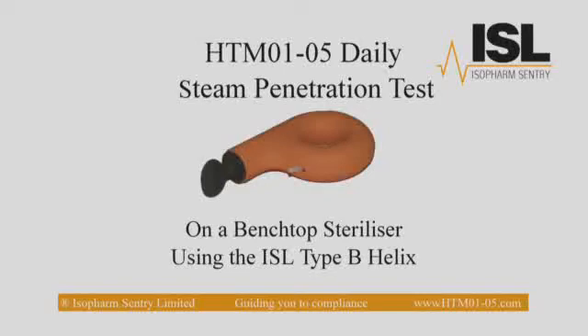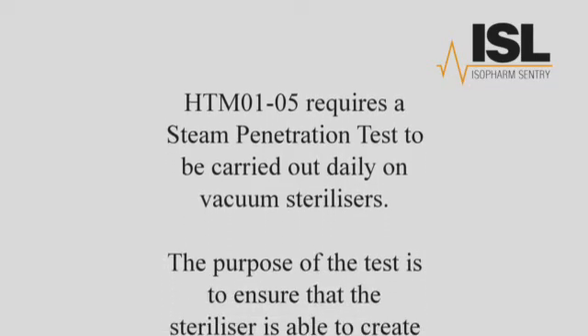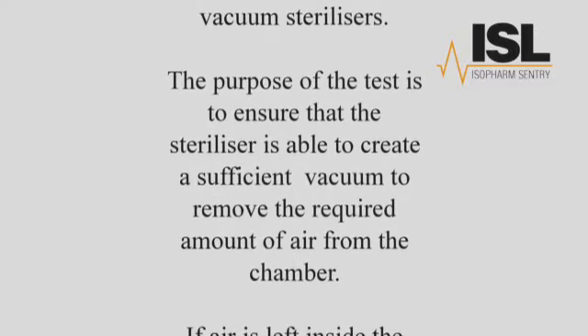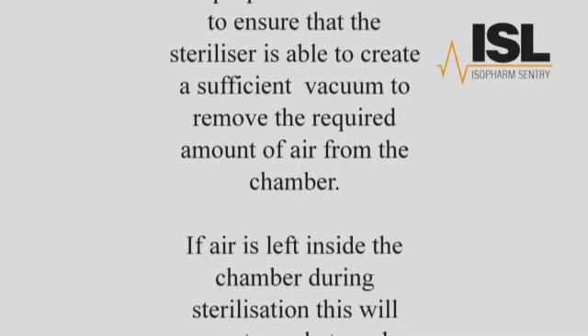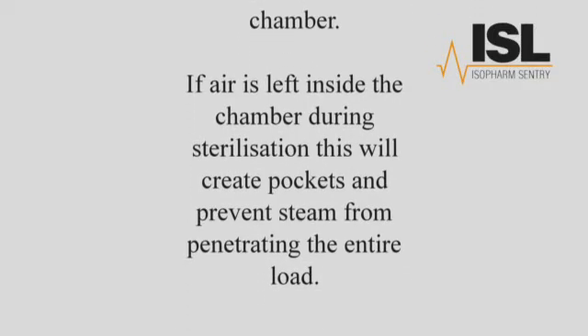HTM01-05 Daily Steam Penetration Test on a benchtop steriliser using the ISL Type B Helix. HTM01-05 requires a steam penetration test to be carried out daily on vacuum sterilisers. The purpose of the test is to ensure that the steriliser is able to create a sufficient vacuum to remove the required amount of air from the chamber. If air is left inside the chamber during sterilisation, this will create pockets and prevent steam from penetrating the entire load.